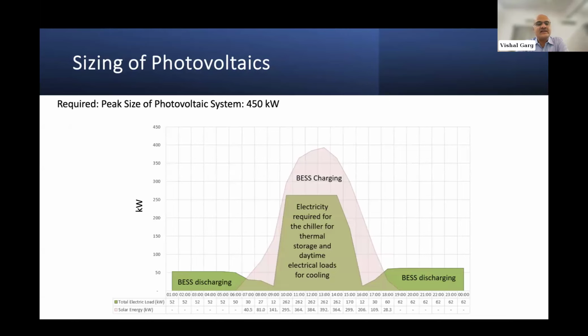So this is the sizing of the photovoltaics. We need 400 kilowatt peak of photovoltaic system, which will generate enough energy in the daytime to not only charge the thermal storage system, but also the battery electrical storage system, the battery energy storage system. And that means overall nighttime air conditioning consumption would be 100% shifted to photovoltaics.